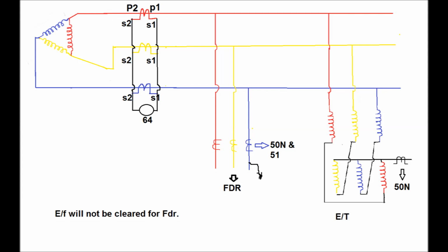So there will be voltage stress in the red phase and yellow phase winding, and also the equipment connected to the red and yellow phase, and as a result equipment failure, CT burst out or LA burst out, and again BPI, that is bus post insulator burst out, can occur, and it may also damage the winding of the transformer.